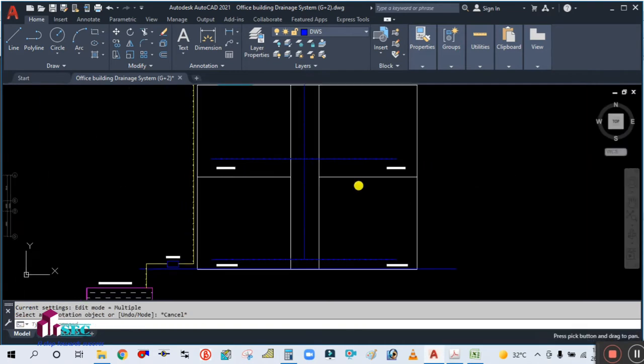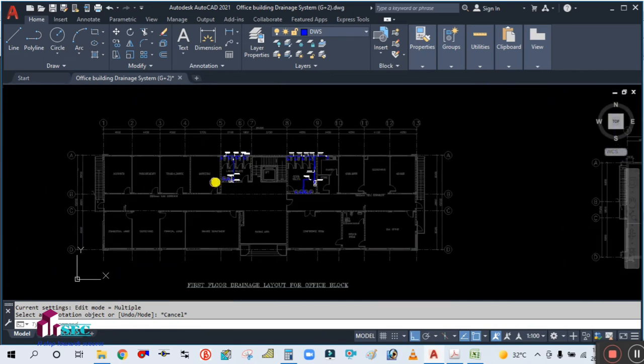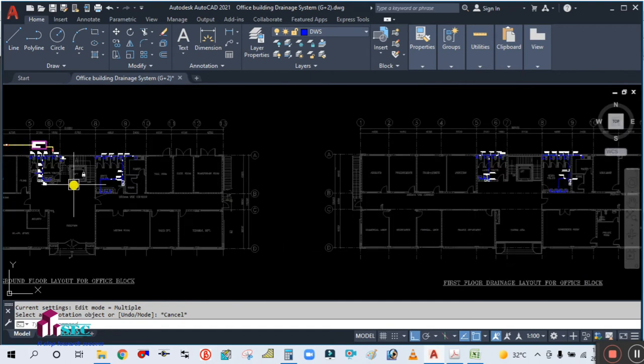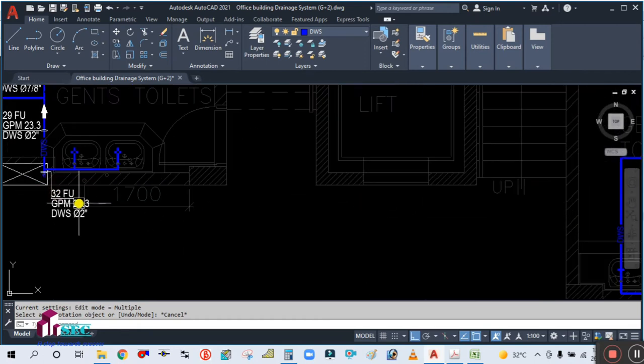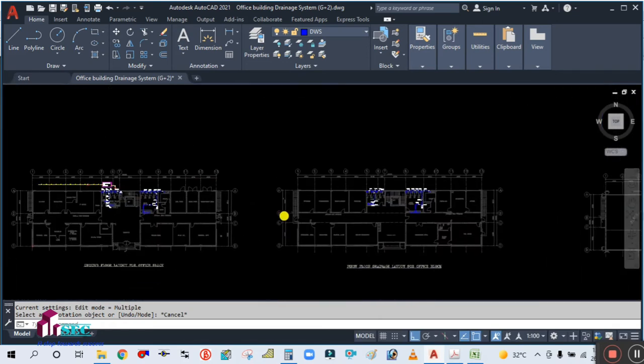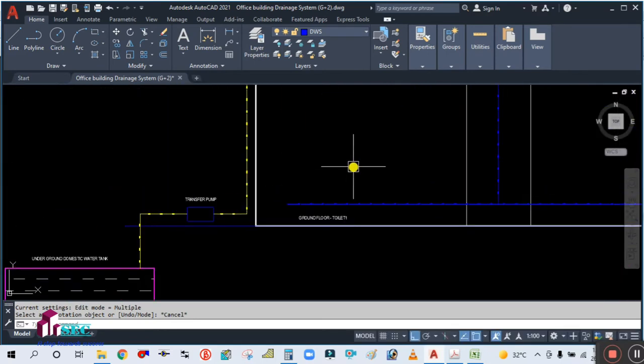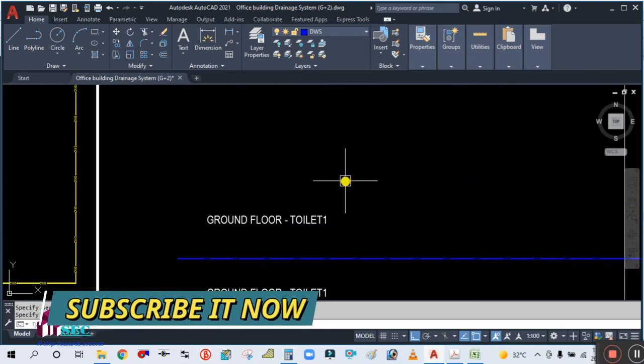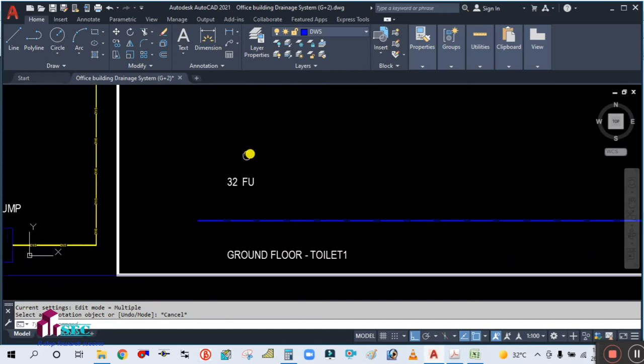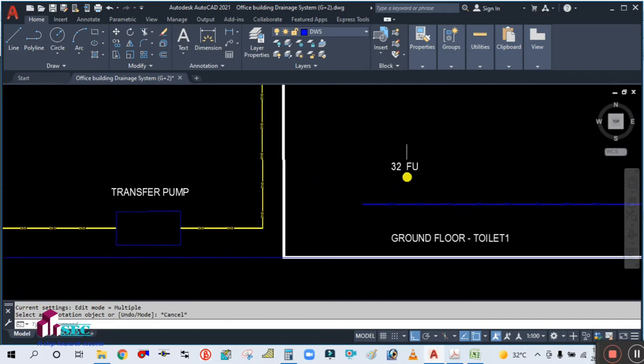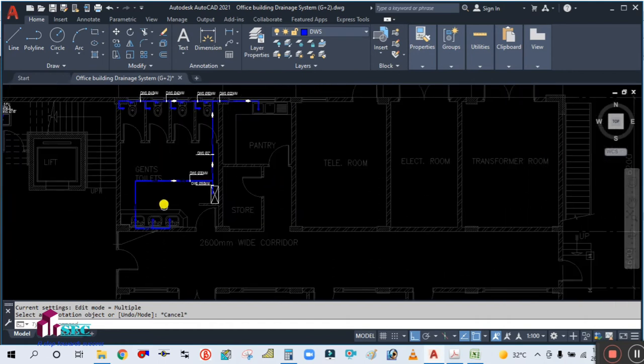Now we have to write the GPM. For the ground floor, 32 fixture units — the GPM is 23.3 and diameter is 2 inch. So here will be your 32 fixture units. We have to copy this one and place it here. GPM is 23.3 and pipe size is 2 inch.